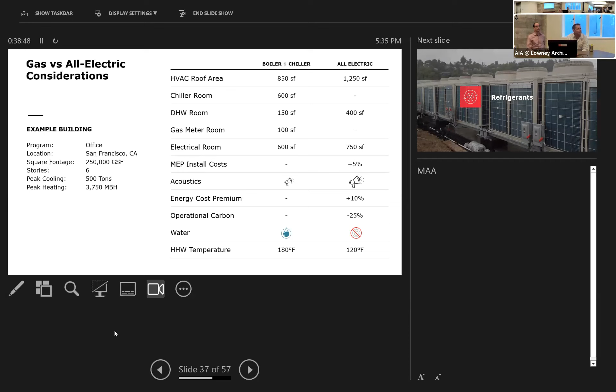With air source heat pumps, there's no water use in the heat rejection, whereas if you've got a water-cooled chiller, you've got all that water going out through the cooling tower. And then this last line here is the heating water temperature. Typically with gas boilers, you'll generate water at about 160 to 180 F, whereas an air source heat pump can only generate 120 F of water. So if you're doing a retrofit from gas boiler to air source heat pump, it's not as easy as all that. It's not just taking one out and plugging in the new machine. You may have to increase your pipe sizes, your pumps, and it can affect your coils as well. If you've selected your heating coils in your air handlers for 180 F, you won't get anywhere near the heat output if you go to 120. So, yeah, retrofits of existing systems can be tricky.